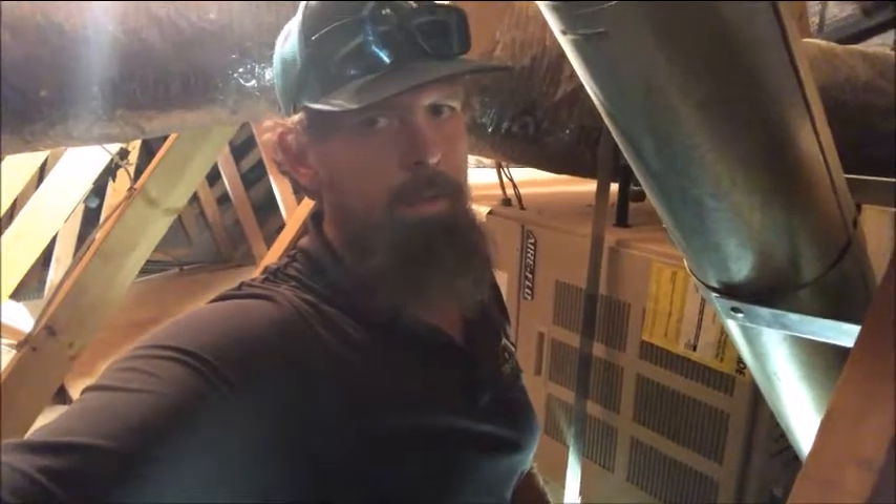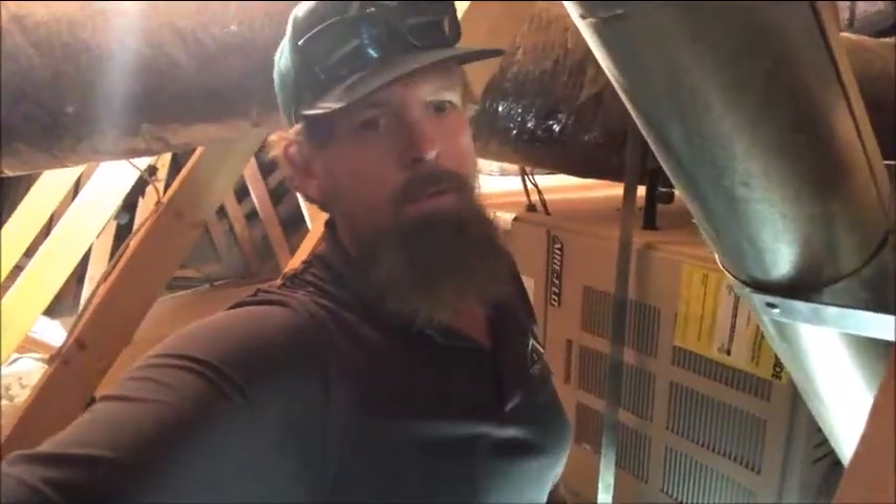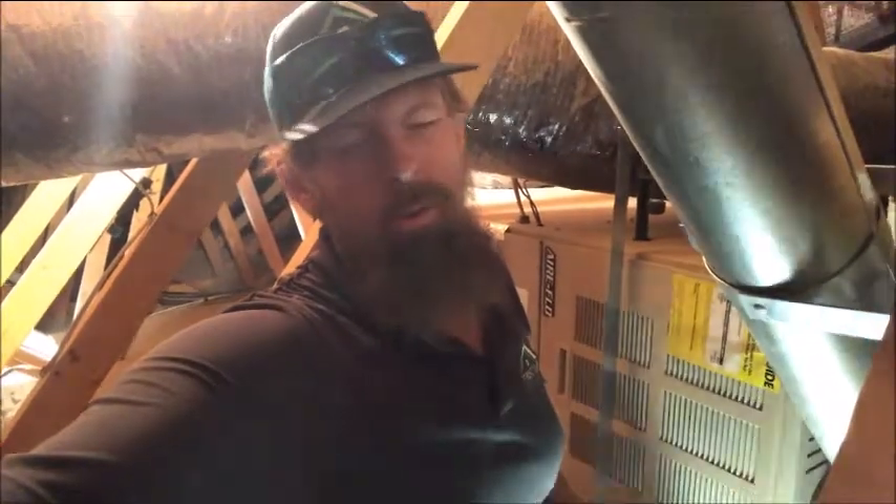Hello, Nick with First Class Home Inspections. We're testing an AC in a furnished unit, and you can basically hear the rattle in the background. This probably means the squirrel cage is wearing out, so failure might be coming soon. We're going to recommend further evaluation by an HVAC company to make sure this isn't going to be an issue going forward.